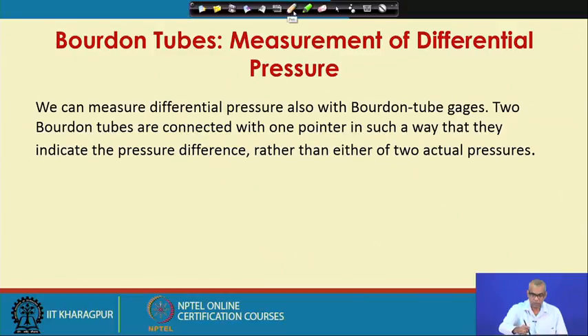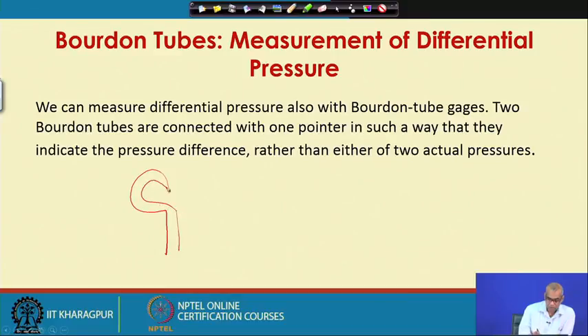Now, Bourdon tube, as we have discussed, measures gauge pressure, because you are applying pressure inside. So, from outside you have atmospheric pressure acting on the tube surface. So, the tip deflection is basically being measured against the ambient pressure. So, it measures gauge pressure, but can I measure differential pressure with Bourdon tube? Yes, we can. We can measure differential pressure also with Bourdon tube gauges.